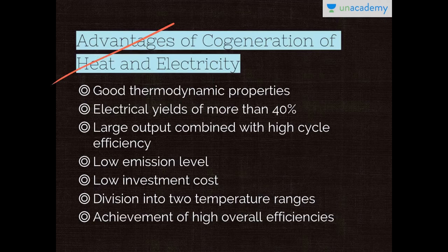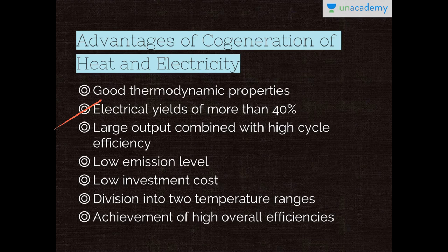Moving on to the advantages of co-generation of heat and electricity. The good thermodynamic properties of combined cycle plants are highly suitable for co-generation of heat and electricity. Electrical yields of more than 40% are quite common in industrial power plants with back-pressure turbines. Large output combined with high cycle efficiency, low emission level and low investment cost are the main attractive features of combined cycle power generation. It also helps in the division of the expansion process in two temperature ranges — 1100 to 550 degrees centigrade — achieving overall efficiencies exceeding the 50% range.